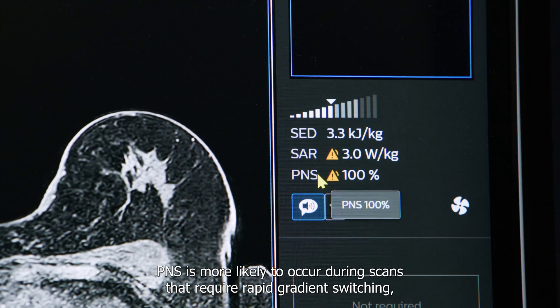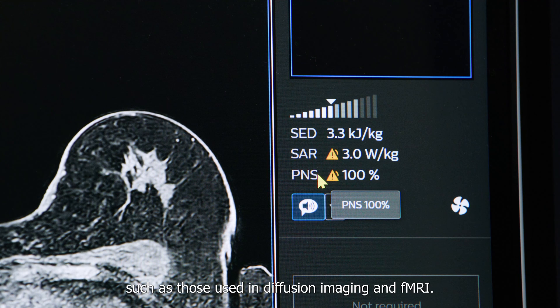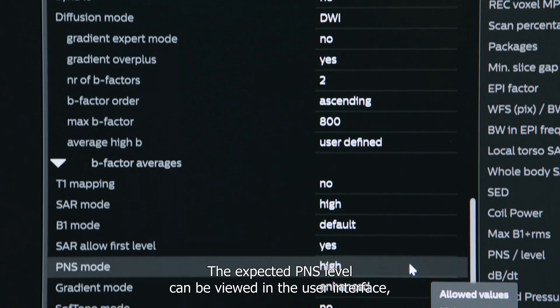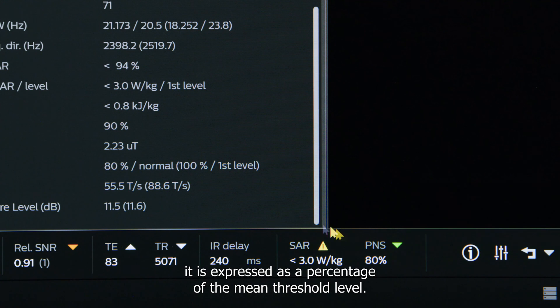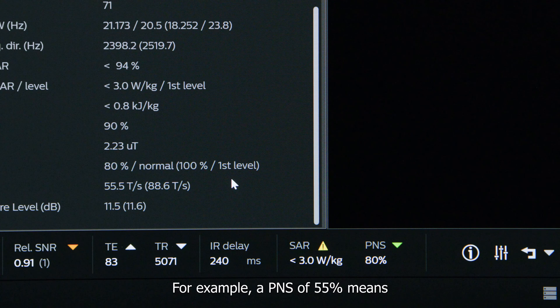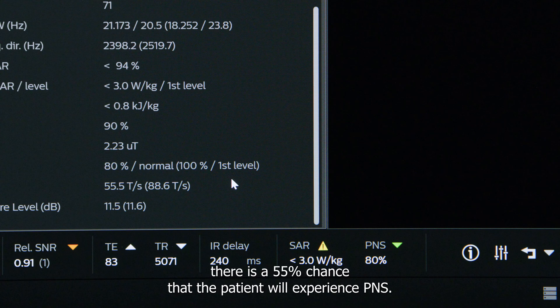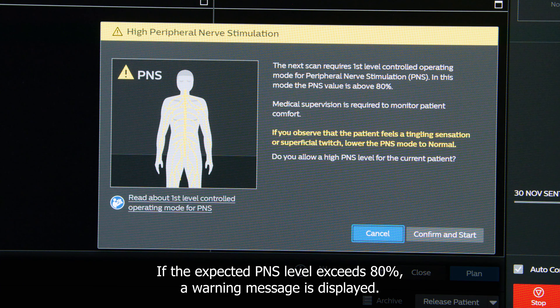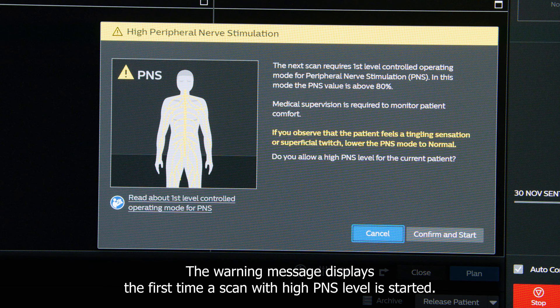PNS is temporary with no known long-term health effects. PNS is more likely to occur during scans that require rapid gradient switching, such as those used in diffusion imaging and fMRI. The expected PNS level can be viewed in the user interface, expressed as a percentage of the mean threshold level. For example, a PNS of 55% means there is a 55% chance the patient will experience PNS. Scans with high PNS can be identified by a warning icon, and if the expected PNS level exceeds 80%, a warning message is displayed.